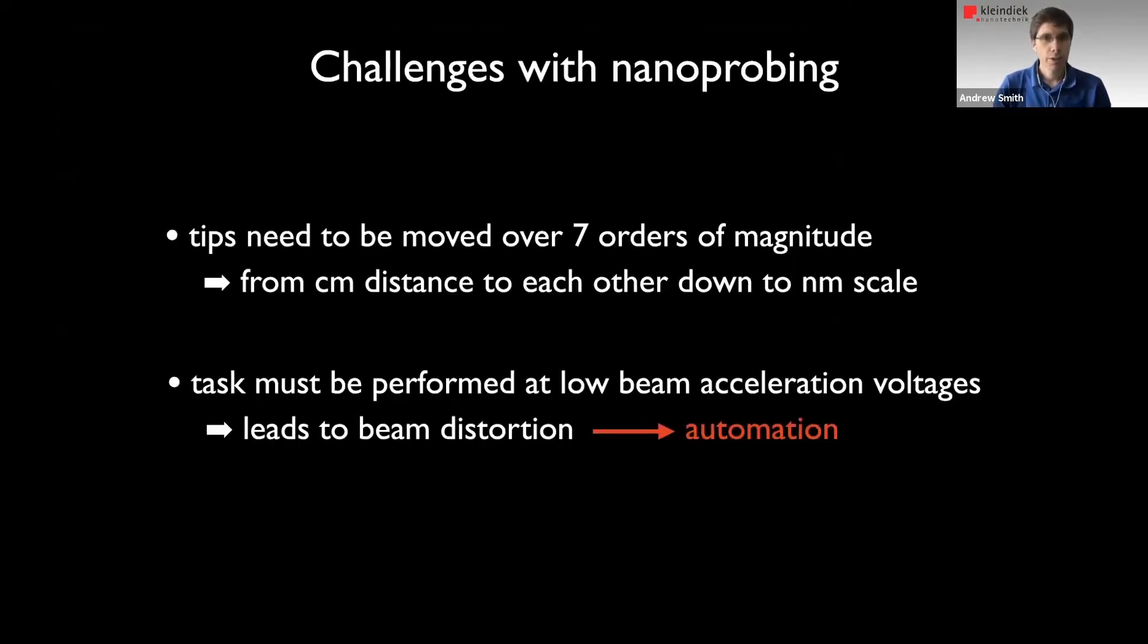Another challenge we have is we have to bring our probe tips, which have some nanometers of tip radius, from centimeters of distance down to nanometers close to each other. And that's seven orders of magnitude. And as we just discussed, we have to do this at very low acceleration voltages. And since moving the probes around at these low voltages causes the beam to distort and shift, the only solution is to do this with some form of automation.